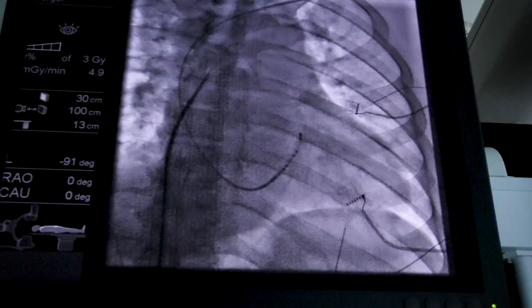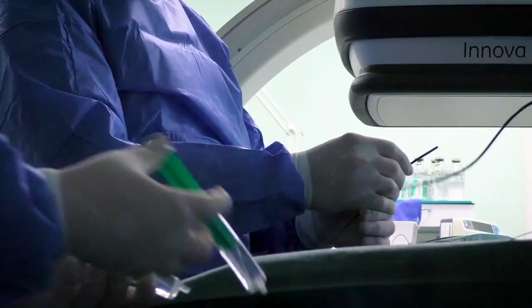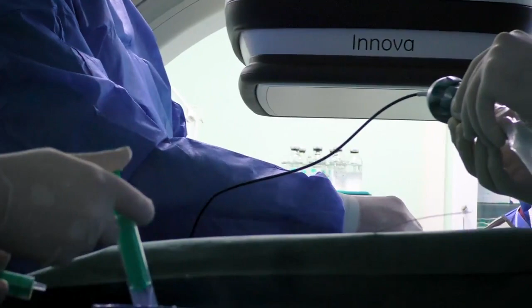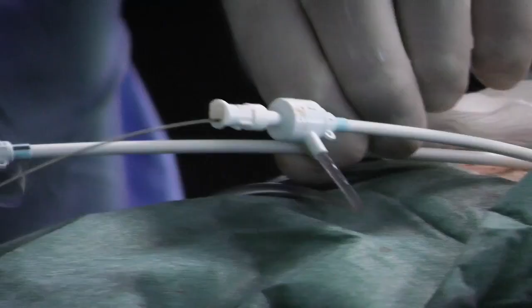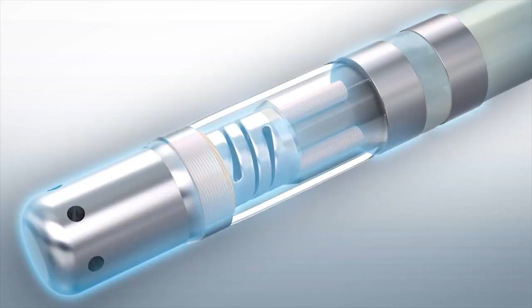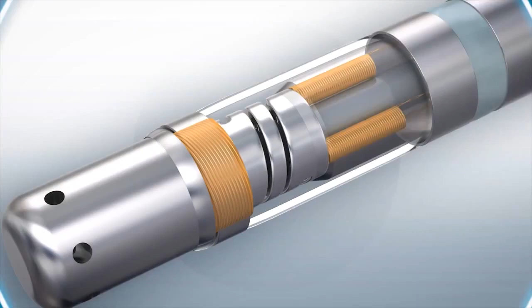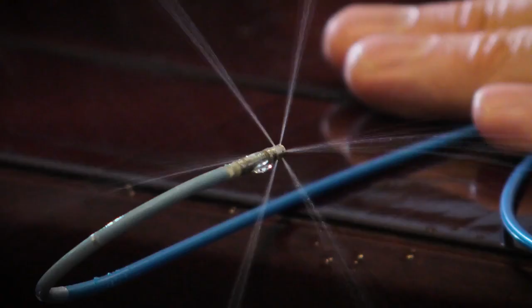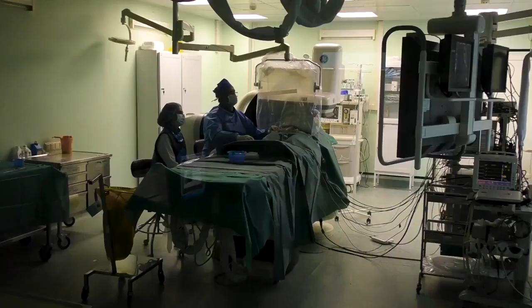Saline is being delivered constantly to the area of ablation through the 6 small openings. It prevents the tissue from overheating and as a result reduces the risk of thrombosis and increases the depth of damage. Several sensors are built into the tip of the catheter. There are several sensors on the tip of the catheter. A pressure sensor, a temperature sensor, and a 3D magnetic location sensor. There are poles on each of the 3 3D coordinate axes which record electrical signals. There are also openings through which saline is supplied.